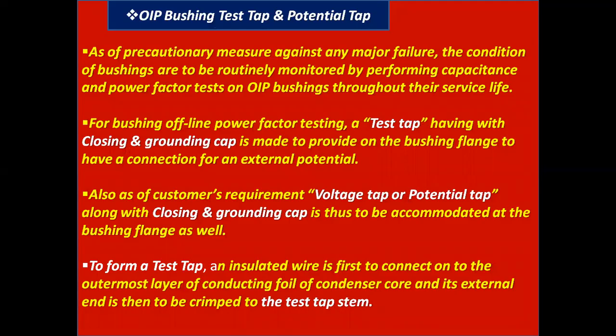Let's start with OIP bushing test tap and potential tap. As a precautionary measure against any major failure, the condition of bushings is to be routinely monitored by performing capacitance and power factor tests on OIP bushings throughout their service life.